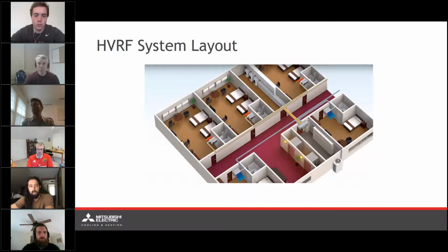So just a top-down layout of what we're looking at here, just to drive home the point of how much refrigerant we're going to be removing from the system. On the bottom right, we have the condenser unit outdoors, serving refrigerant piping indoors to the hybrid BC controller that's in this closet. And that's all we need to account for with ASHRAE 15, ASHRAE 34, refrigerant concentration limits. We don't need to worry about any refrigerant running through occupied spaces, running through apartment units, condos, anything of that nature, anywhere anyone's going to be sleeping. It's an item of concern that I've heard come up, that we don't want refrigerant piping in a space where someone's sleeping for one reason or another. However conservative you are in your designs, you want to remove the refrigerant from that space. This is how we could potentially accomplish that.